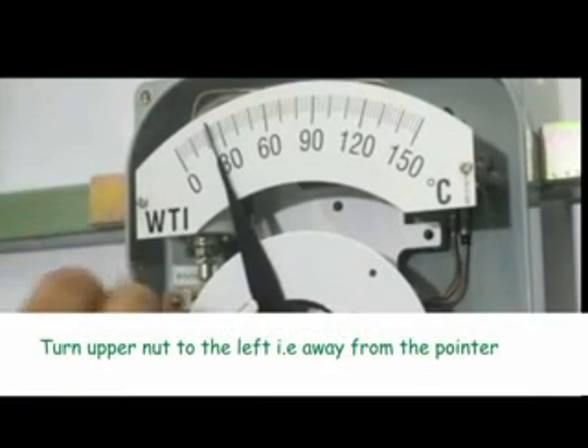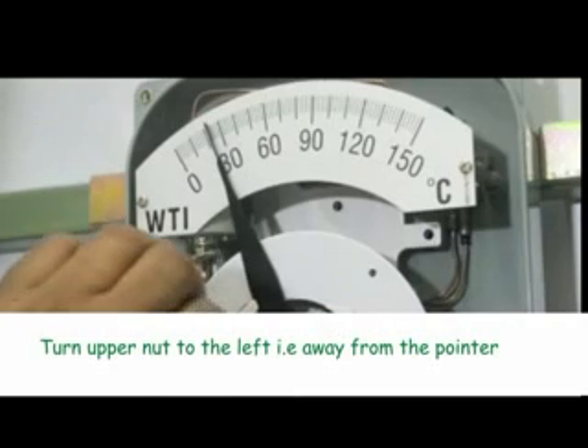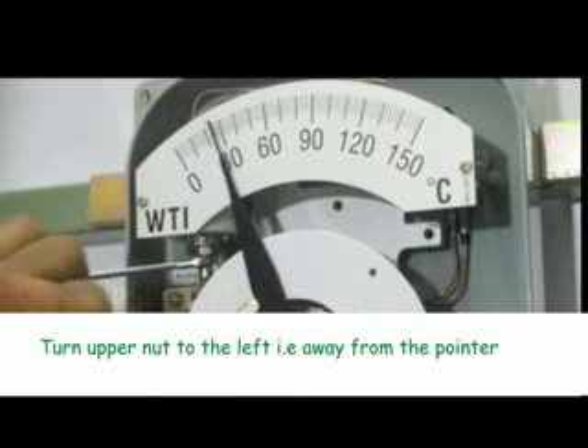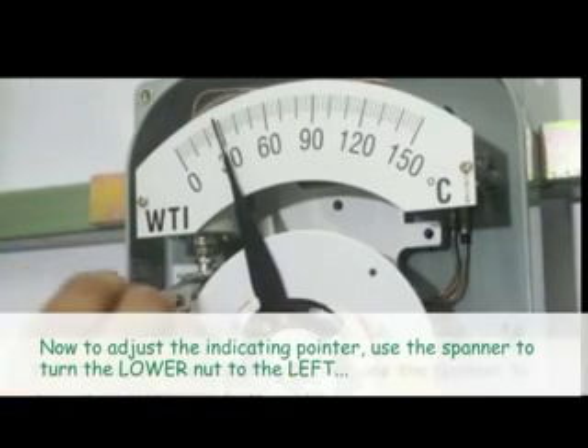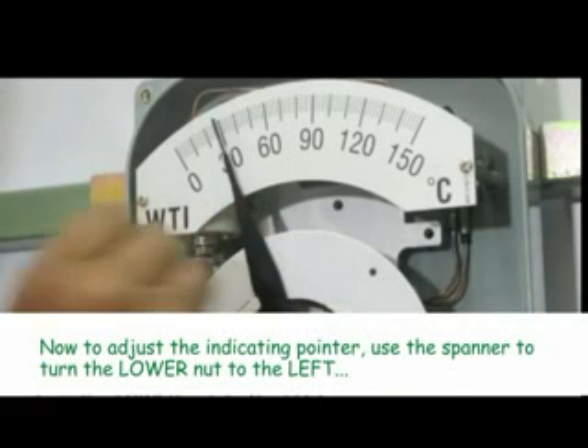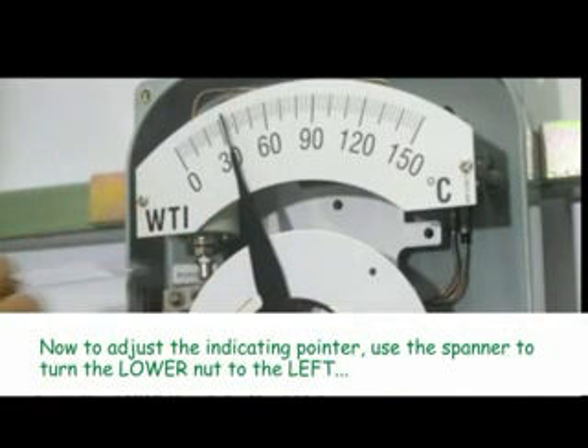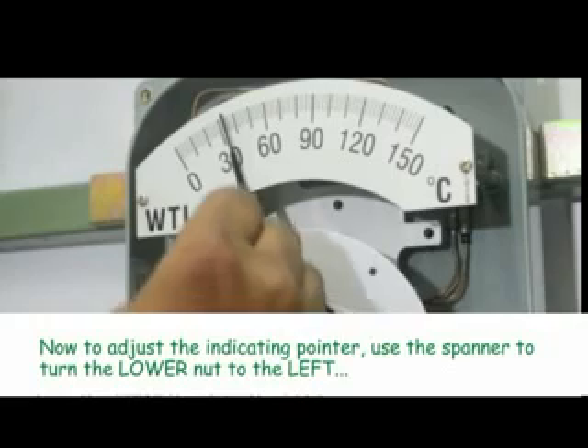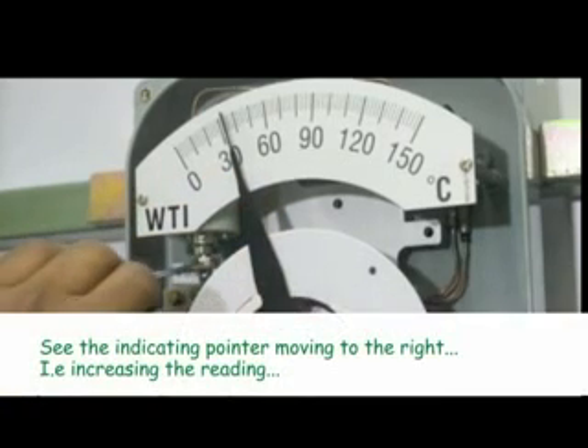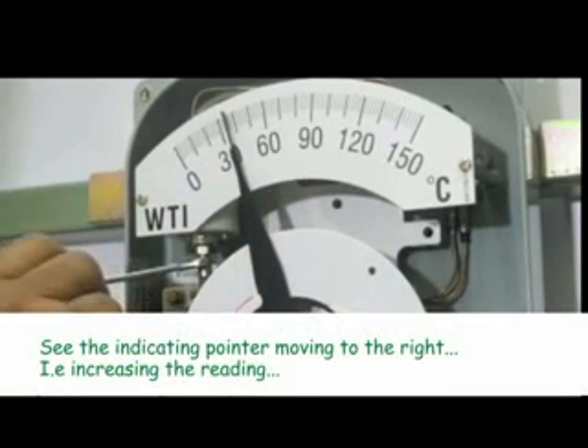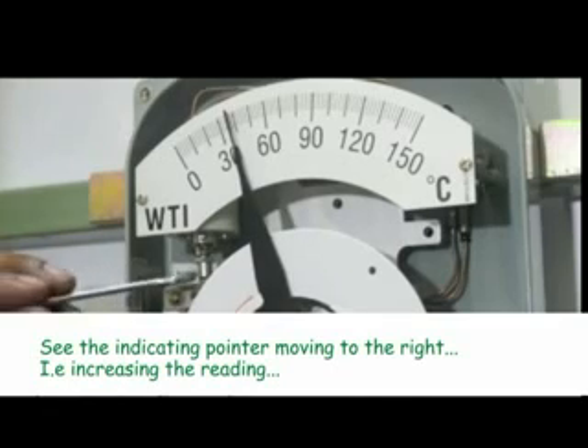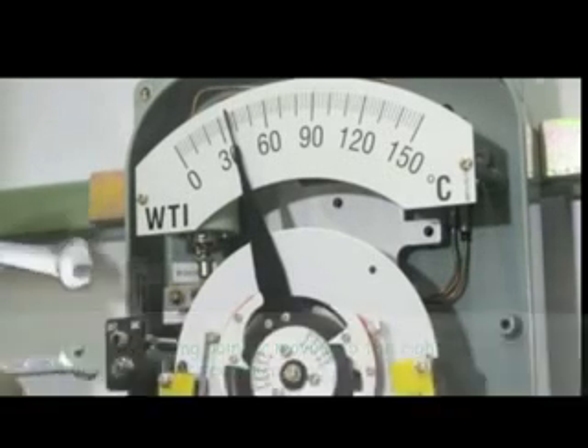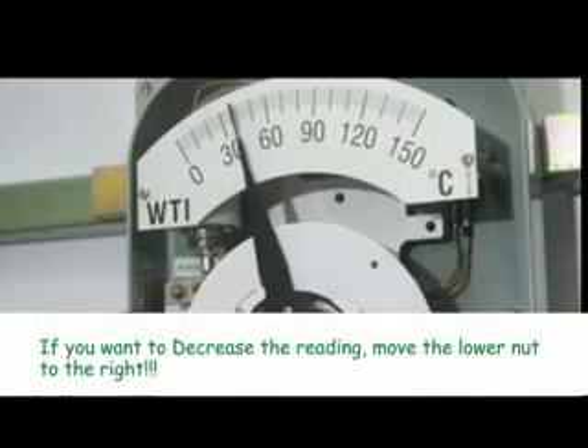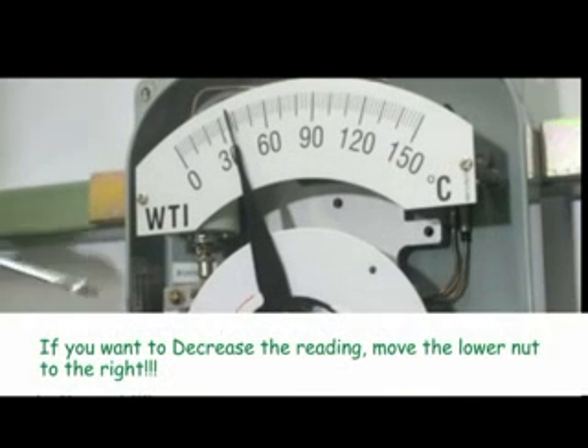Turn the upper nut to the left, that is, away from the pointer. Now, to adjust the indicating pointer, use the spanner to turn the lower nut to the left. See the indicating pointer moving to the right, that is, increasing the reading. If you want to decrease the reading, move the lower nut to the right.